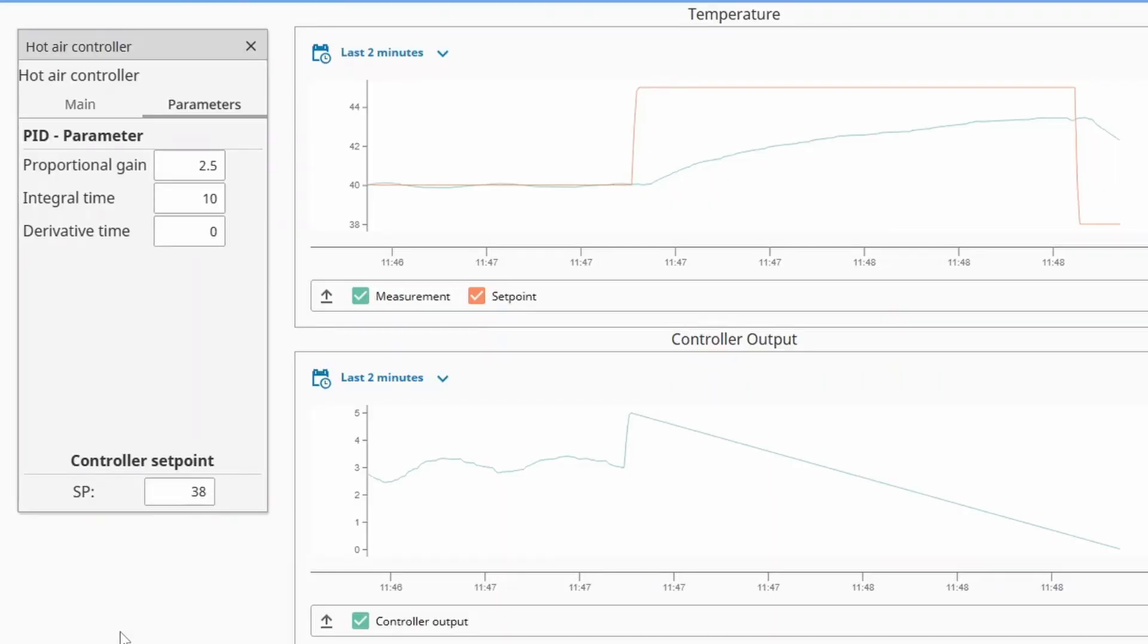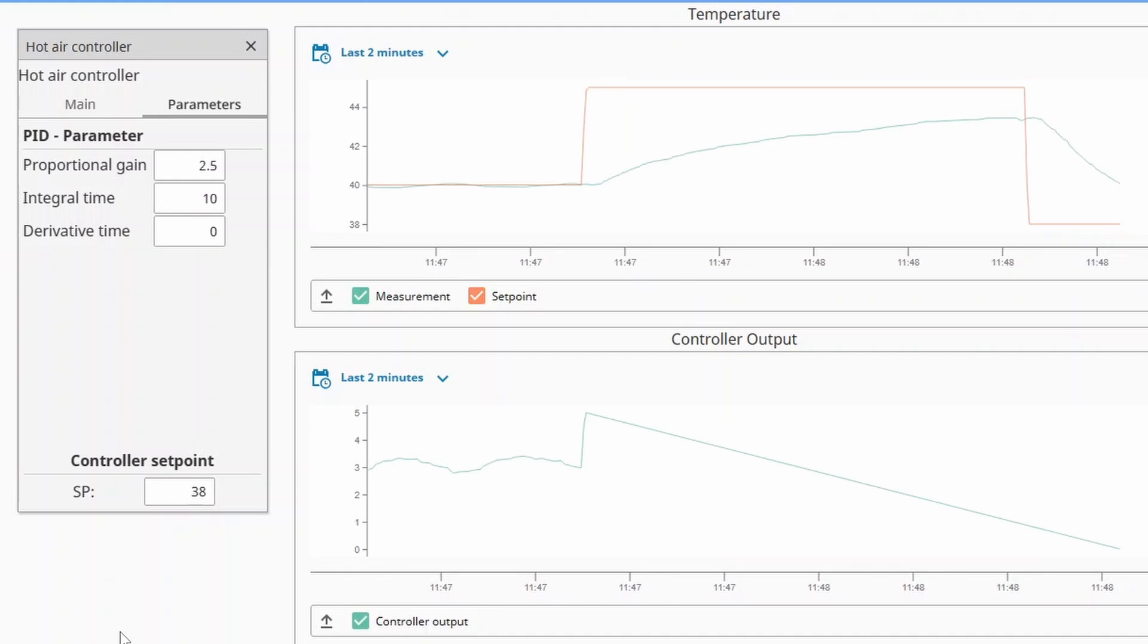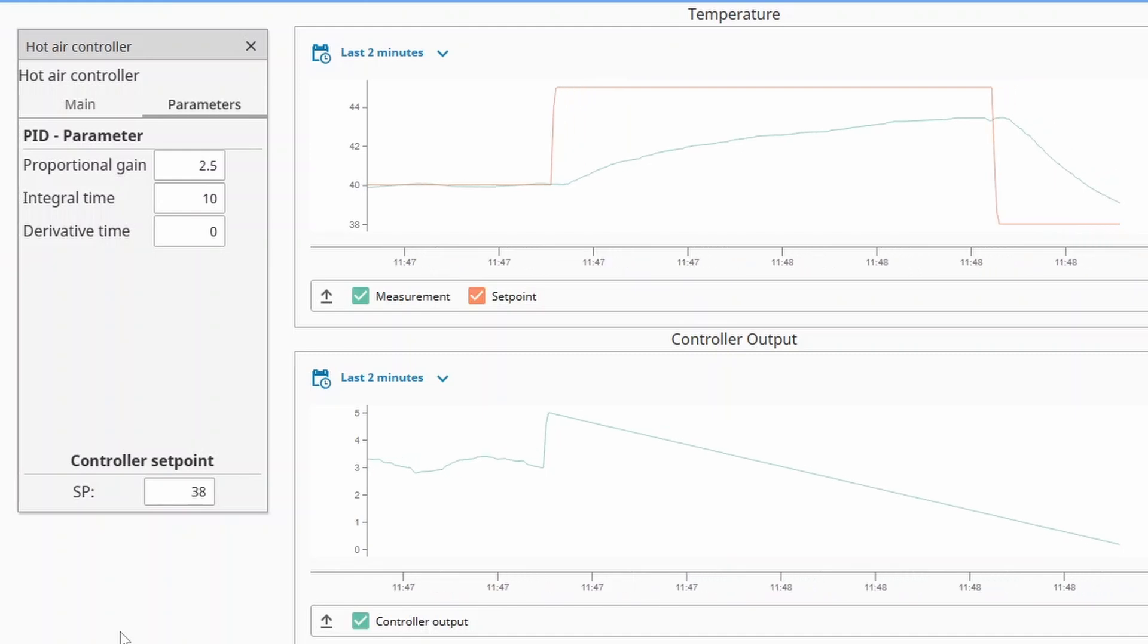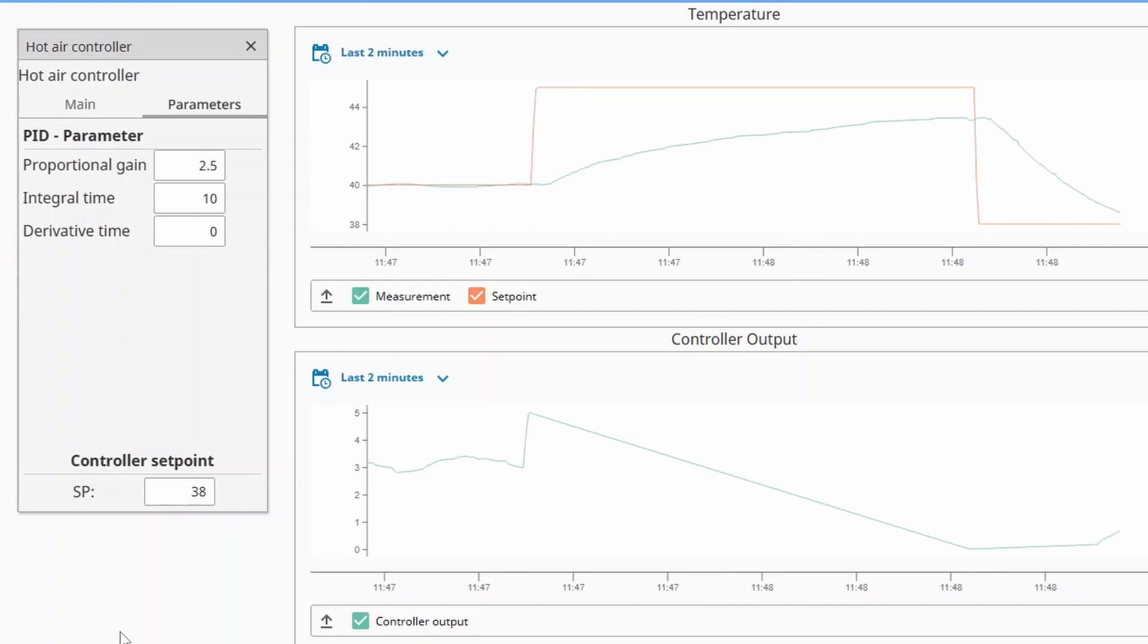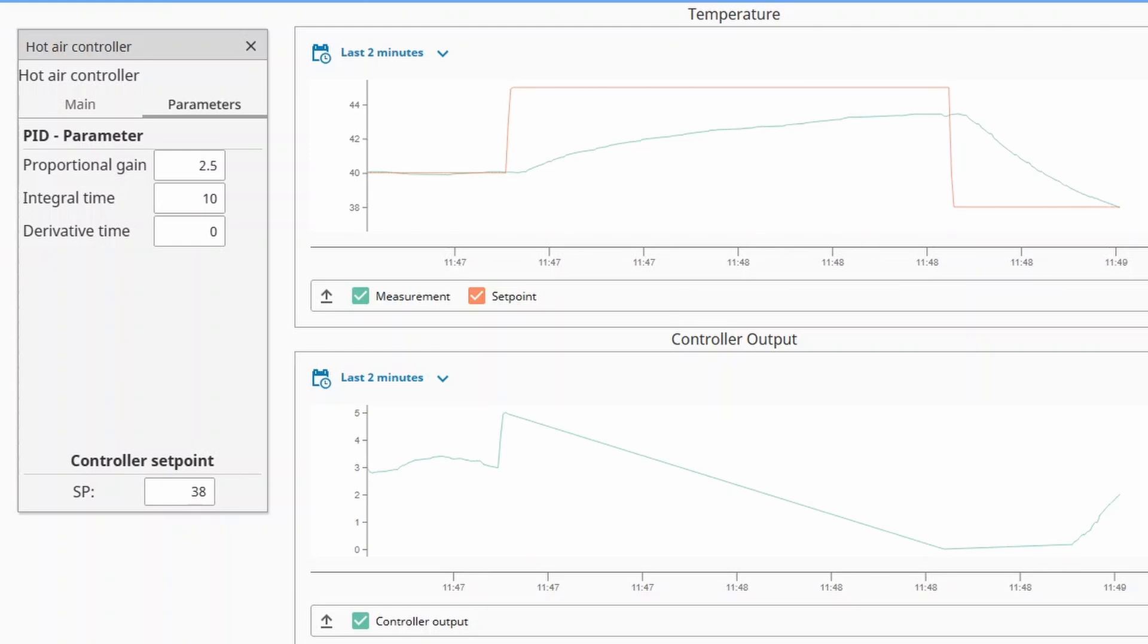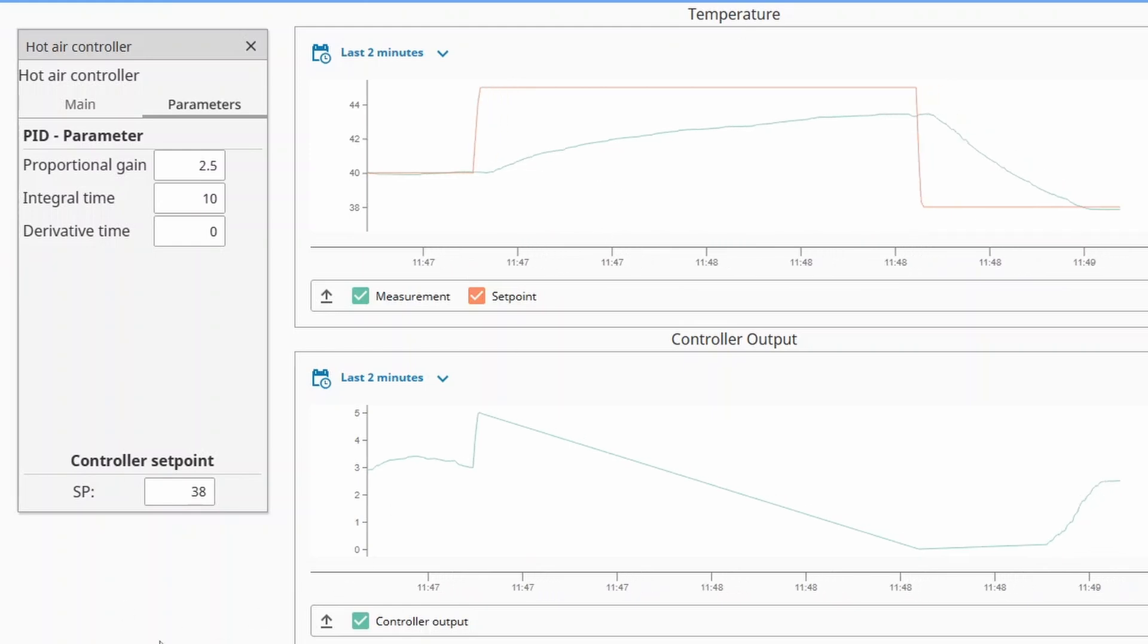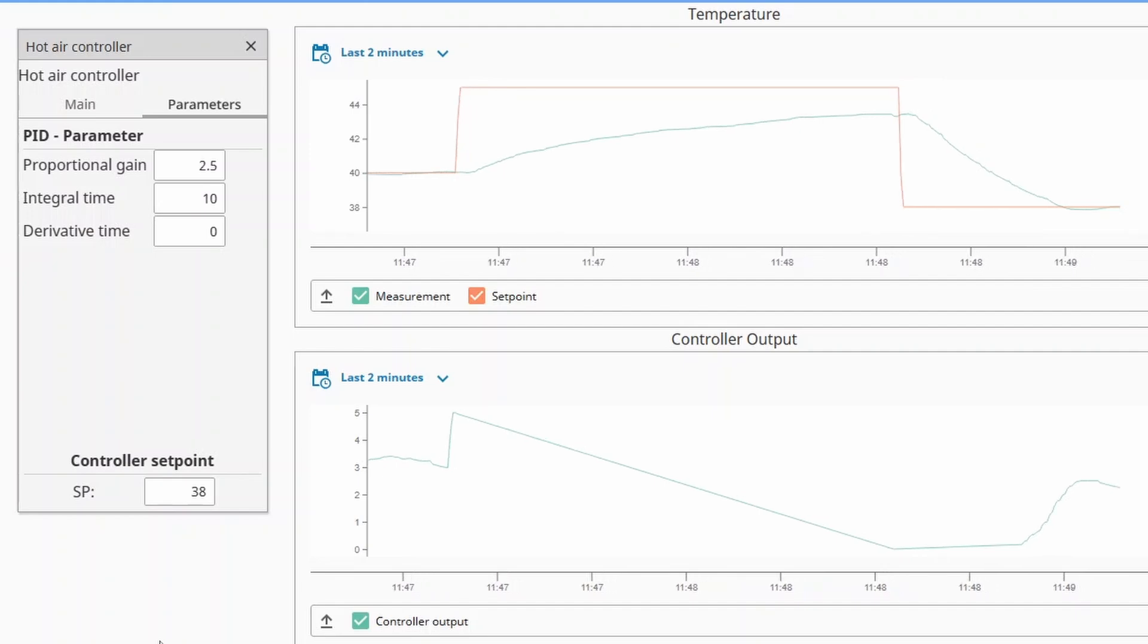As you see on the trend lines the process now responds good after a step change in the setpoint. I just moved the setpoint down to 38 degrees and the heating element has now stopped heating completely to allow the temperature to fall down. Now it's getting closer and the heating element starts carefully to heat. It will settle around the heating power where it finds the equilibrium. We will give it some time to settle.